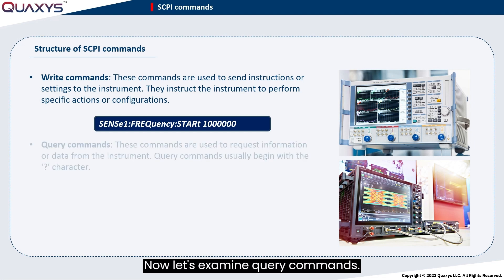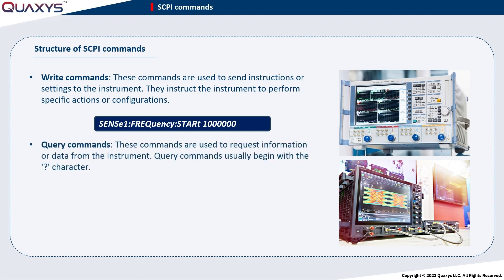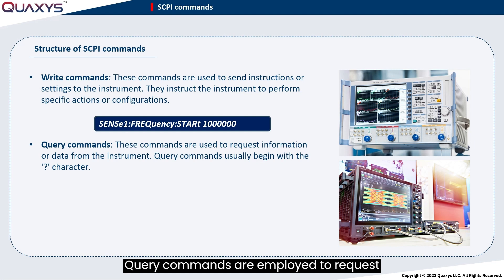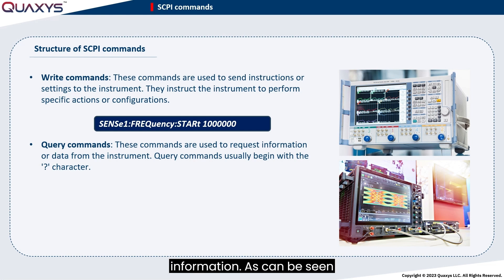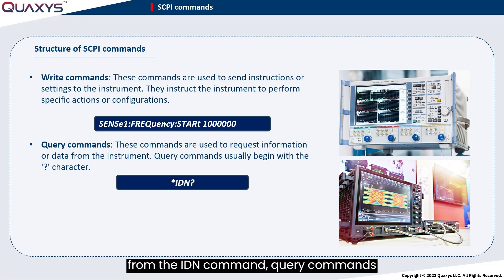Now let's examine query commands. Query commands are employed to request information or data from the instrument. They prompt the instrument to provide a response containing the requested information. As can be seen from the IDN command, query commands typically feature a question mark character.